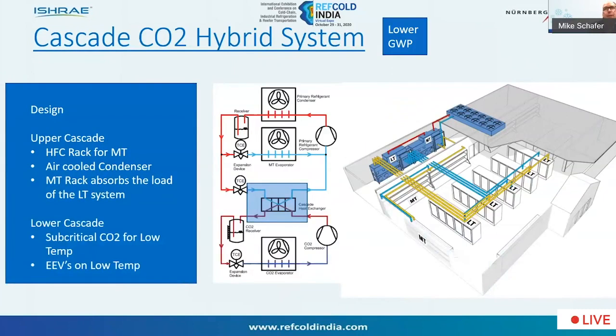So the next system we'll look at is a cascade CO2 hybrid system, another lower GWP architecture or strategy being employed. In this particular case, there's essentially two racks, the lower cascade and the upper cascade. The low temp would be in the lower cascade, and that would be operating subcritical CO2. It would have EEVs on the systems, and then that would be rejecting that heat through a cascade heat exchanger, and that load would be carried by the medium temp system.